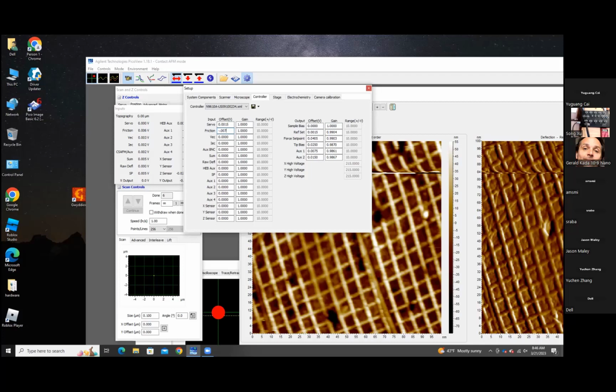And this is why the head electronics box will display a slightly different value than the software, because the head electronics box is taking the raw reading. The software is calibrating that reading based on this file and is displaying a slightly different reading than what the hardware is showing. If you recalibrate your inputs, that issue should go away on your system.